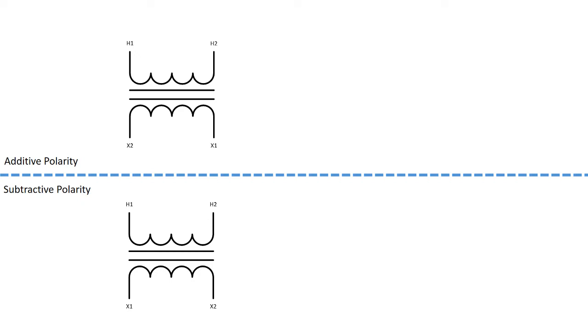The easiest way with an additive polarity transformer is to look at your H1 and X1 terminals. In an additive polarity transformer you'll notice that they're diagonally across from each other. This indicates that we have an additive connection, whereas when we look at the subtractive polarity you'll notice H1 and X1 are directly across from each other. So that's the thing to watch out for—the H1 and X1 terminals.